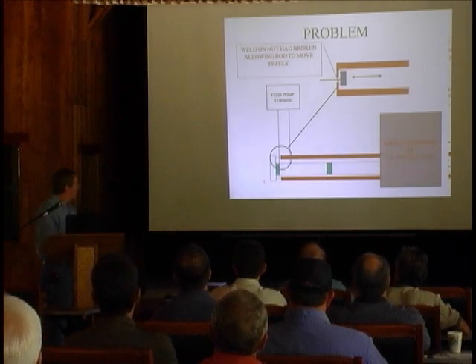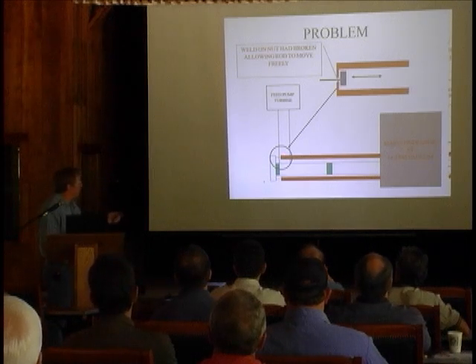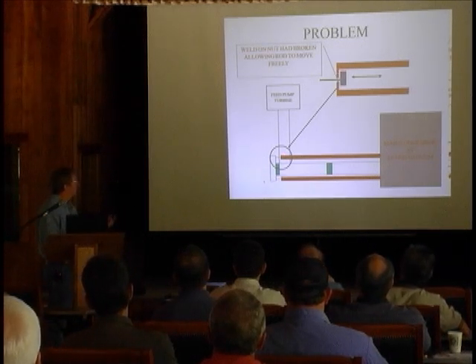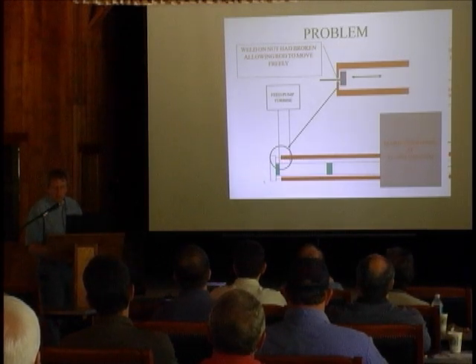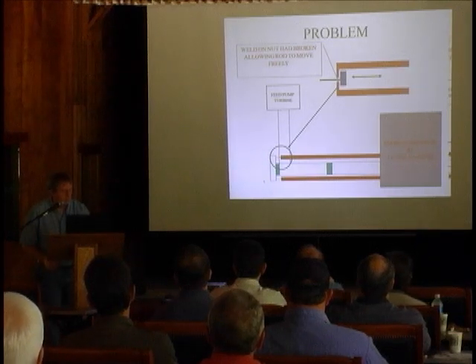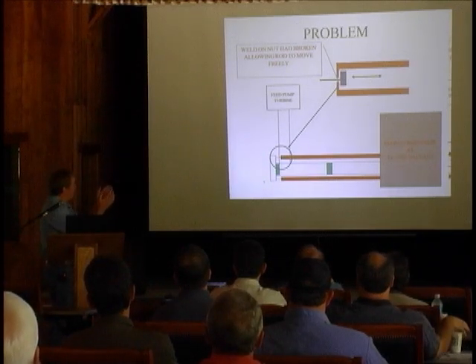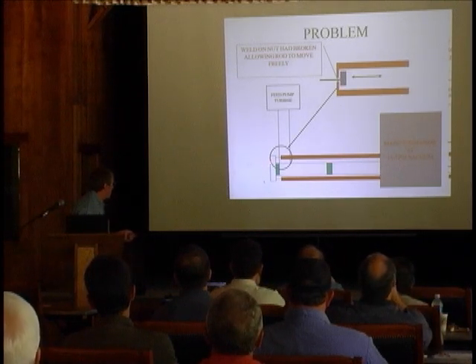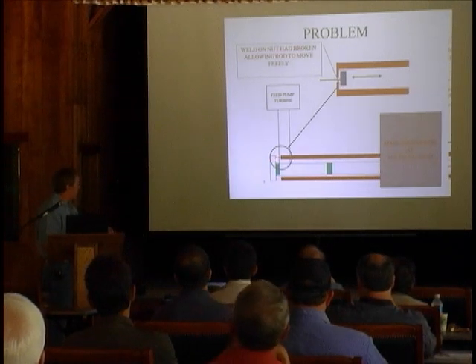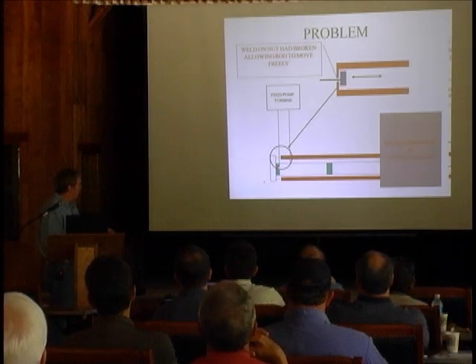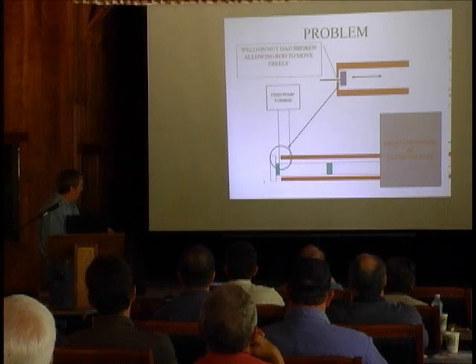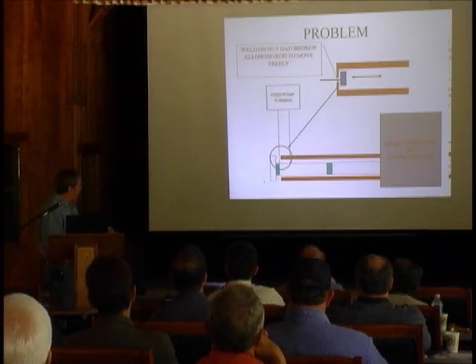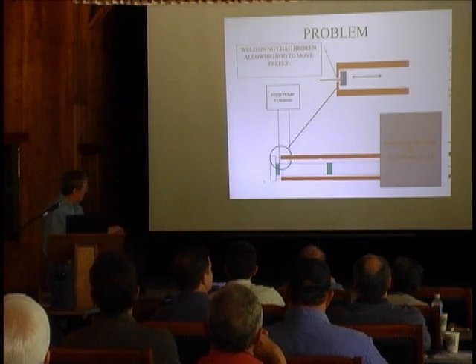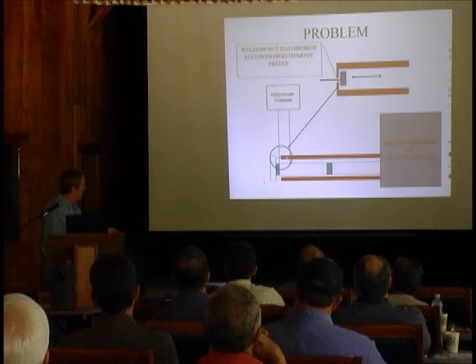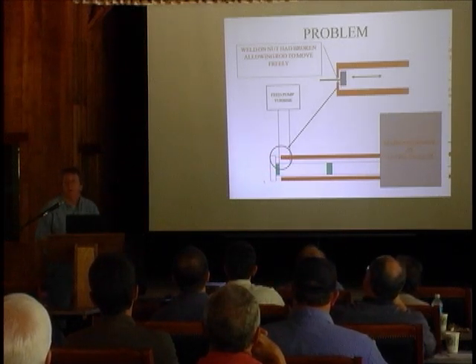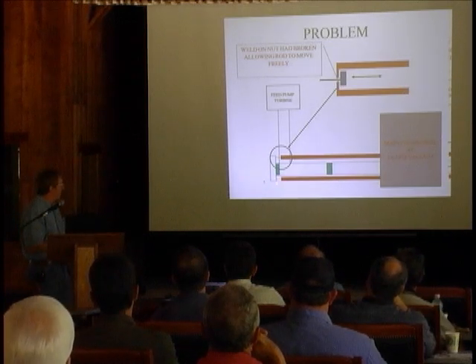And what I discovered was that on these thrust canceling rods, again, these are big pipes, they have a nut right here, a big, huge nut. And then they have, it's like all-thread rod, and the all-thread rod goes through the nut. And then they can turn that rod, and they can adjust this end cap here and set it wherever they want it. And then whenever you draw vacuum on the turbine, this pipe's under vacuum, and the atmospheric pressure pushes here. It then pushes into the all-thread rod, into the nut, and down these things.